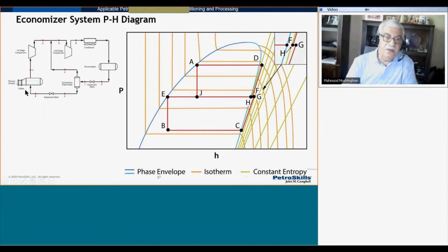Our objective is the same thing: remove 8.1 million BTU per hour heat from process gas at the chiller temperature of -4 degrees Fahrenheit. So my chiller temperature and chiller pressure would be the same as before. My condensing temperature would be the same as before. Simple refrigeration system would use 104 degrees Fahrenheit, and discharge pressure of the second stage would be the same as before. The suction pressure of the first stage would be the same as before. Discharge pressure of compressor of the second stage would be the same as before.